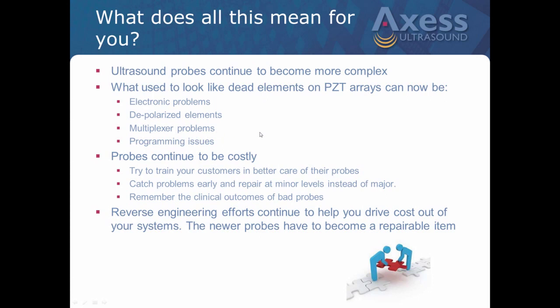Again, what does this mean for you as engineers? Probes are becoming more complex, and they're going to continue to get more complex. There's no question about that. The testing is a big thing, being able to properly identify what's going on. What used to look like dead elements on a PZT array, now in single crystal, can be electronic issues. You can see multiplexing issues, maybe a depolarized array, etc. As you well know, probes are costly if you have to replace them. A huge proponent of this, we do a lot of it actually for customers, is we'll come in and just train a department. Here's how you clean and disinfect and handle a transesophageal probe. Here's how you handle your intracavity probes, etc.